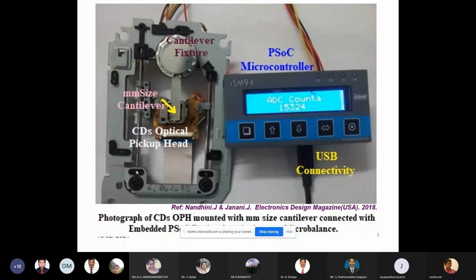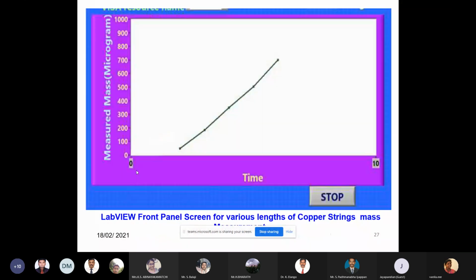Very simple. This appeared in the Electronic Design magazine. This is a measurement where the data acquired in the PC is plotted online. This measurement shows the addition of mass on a simple millimeter-size cantilever, making use of a CD optical pickup head as the readout mechanism. We are not spending crores of money on an AFM; with a simple technique costing 200-300 rupees, even an old CD or DVD drive, one can make use of it.